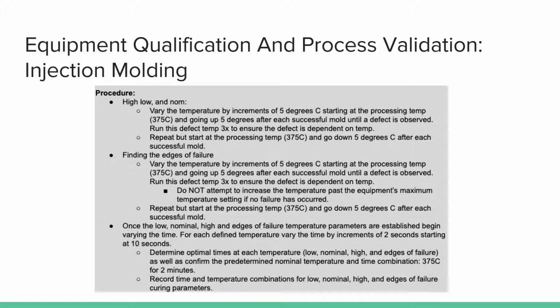Then a process validation was performed to establish the consistency of the normal parameters, which were determined to be 375 degrees Celsius and cooling for 2 minutes. Using 95-99 confidence and reliability and assuming the data was variable, 30 catheters were developed for this testing. A failed catheter means that the dimensions are incorrect and the catheters break when 15 newtons of force is applied to the catheter. The process is deemed successful if a CPK value of over 1.33, which means that the process is capable and meets specification limits.